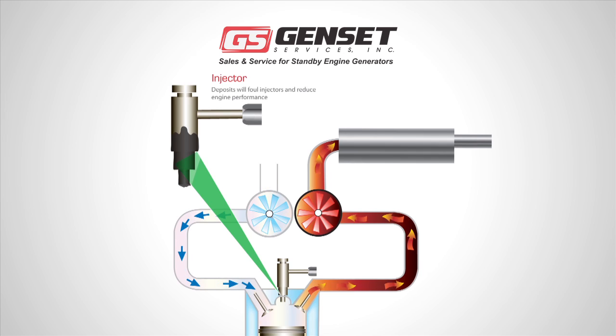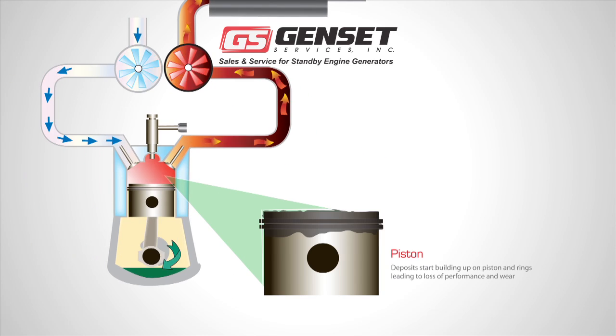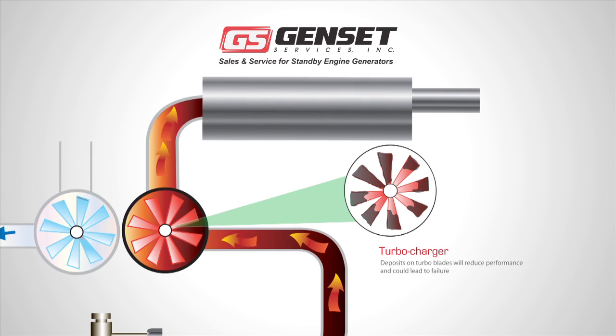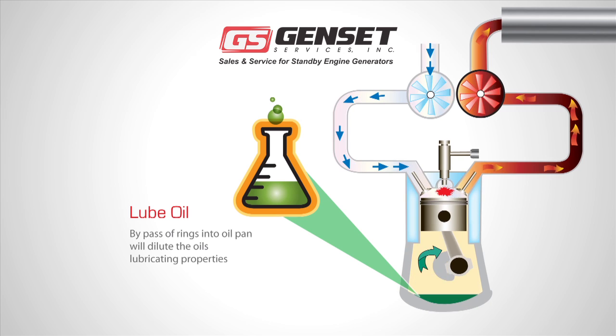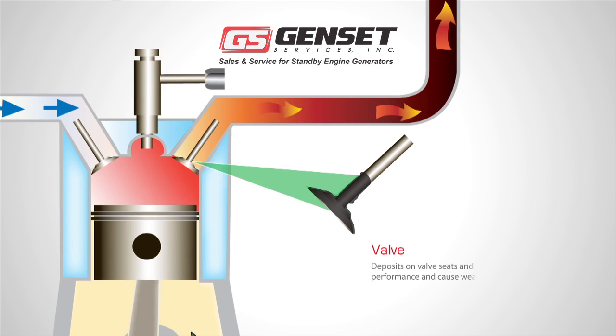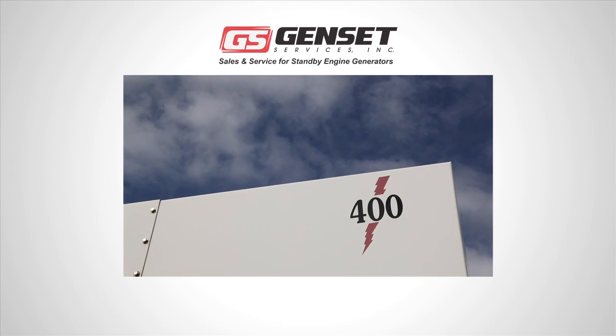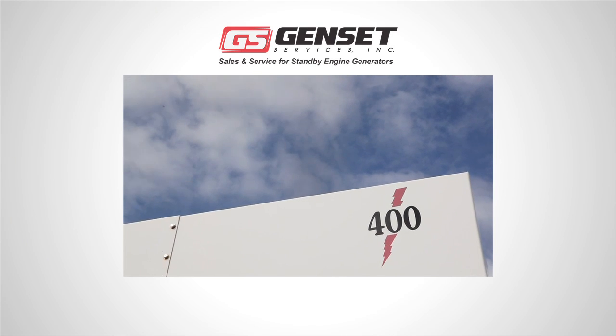Carbon deposits will form on injectors, pistons, rings, turbochargers, valves, and accumulate in the lubrication oil. All of these conditions will result in reduced performance and reduced engine life. Maintenance downtimes are also extended because of the additional work required to remove carbon deposits from key internal components. A frequent sign of an engine suffering from wet stacking is excessive black smoke on startup.